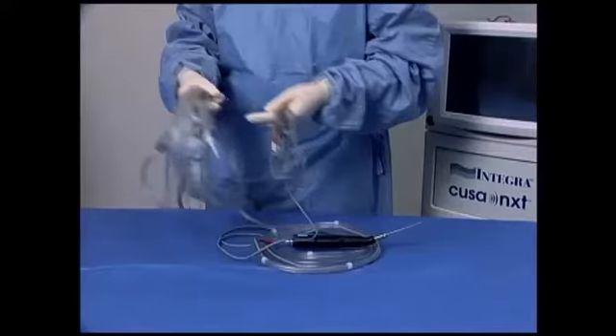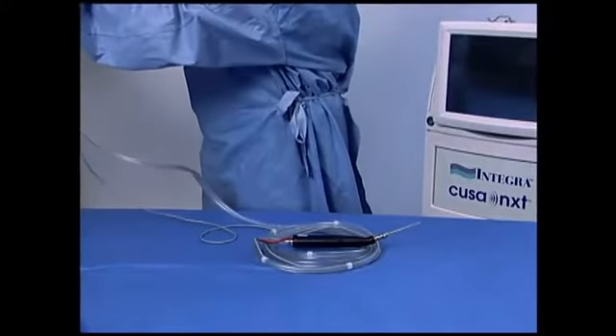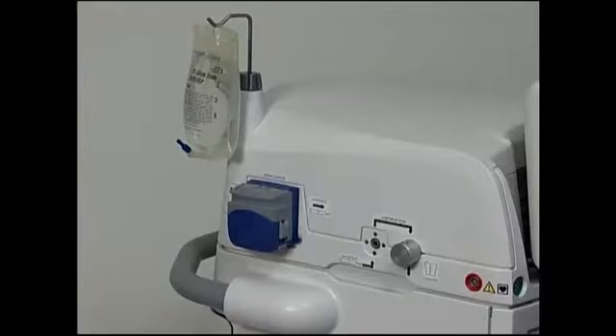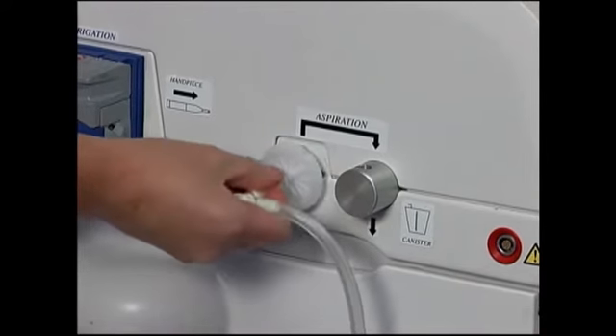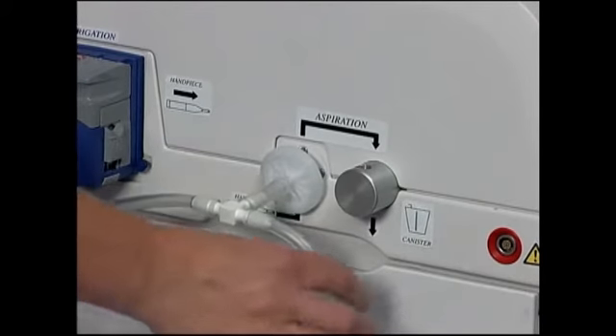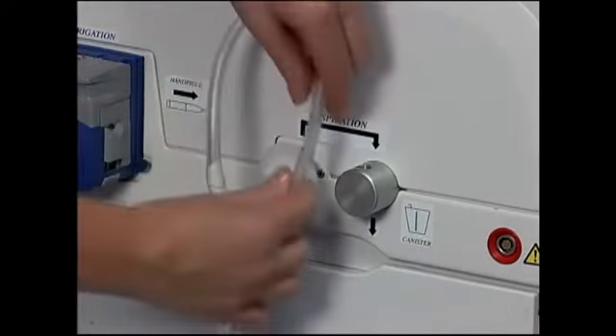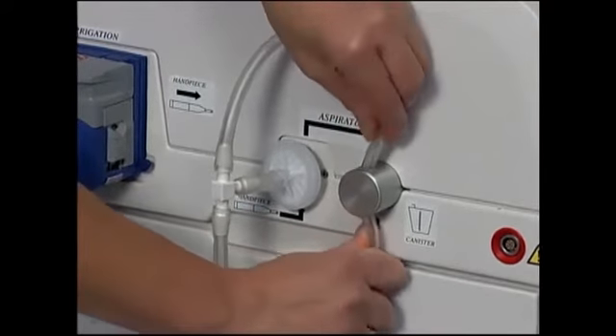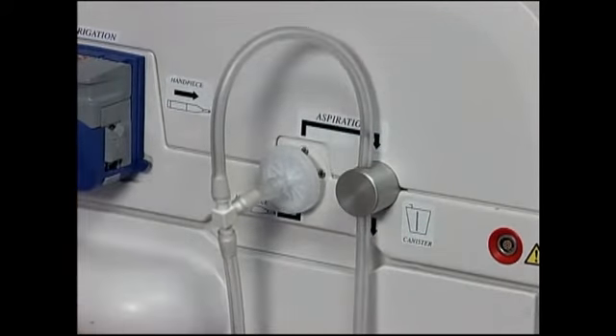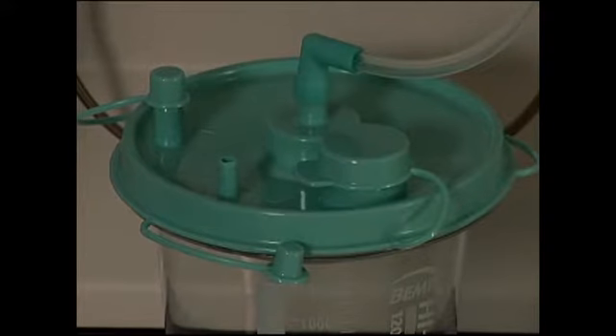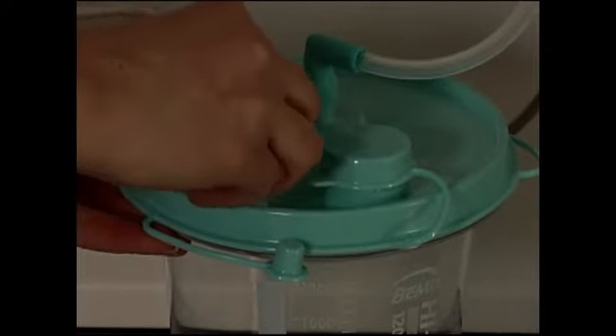Pass the remaining tubing and the handpiece plug off to the circulating nurse. Complete the system setup by routing the tubing through the filter connection port, peristaltic pump, and pinch valve on the side panel of the console. First, push the filter on the tubing kit into the aspiration filter connection port on the left side panel of the console. Next, following the diagram on the left side of the console, route the large bore aspiration tubing through the pinch valve and connect the end of the tubing to the patient port of the suction canister.